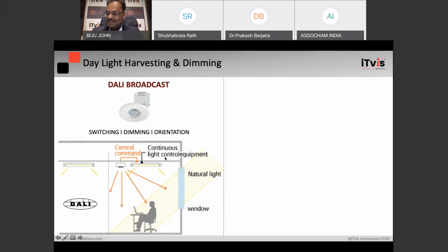What is orientation light? Once you set this orientation lighting percentage, if the sensor doesn't find anyone for a set delay time, instead of switching off the light, it will dim the light to the extent you ask it to. For example, if you set an orientation light of 20%, and the lift lobby has nobody for 10 minutes, the light will dim to 20% and remain there.